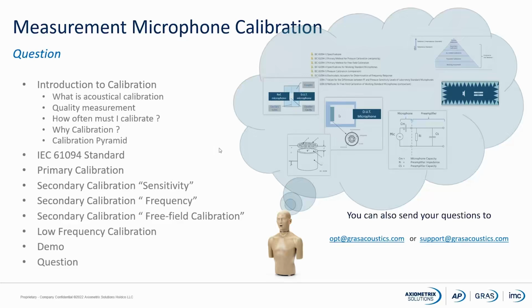In many cases, as I mentioned, I would like to use a pistonphone for my laboratory calibration, and I would normally use a level calibrator for the daily verification, the daily check, whatever we call it. And when we are using the calibrator, it's a good idea to use 1 kilohertz, because then if you one day are using an A filter or another kind of filter, you don't have to take into consideration the damping you have between 1 kilohertz and 250 hertz. So it is a good idea. If you use the calibrator in the field, then use it at 1 kilohertz.